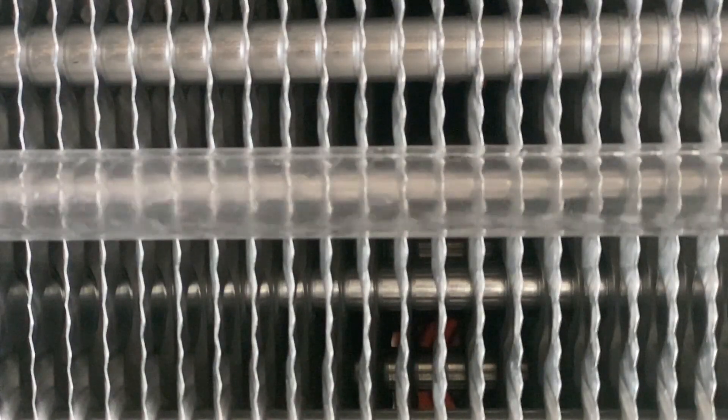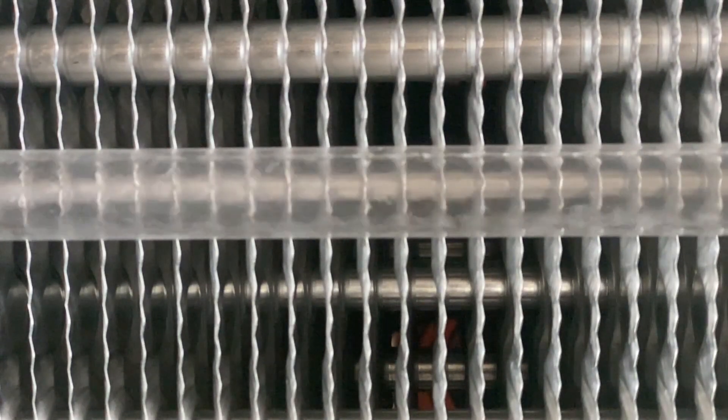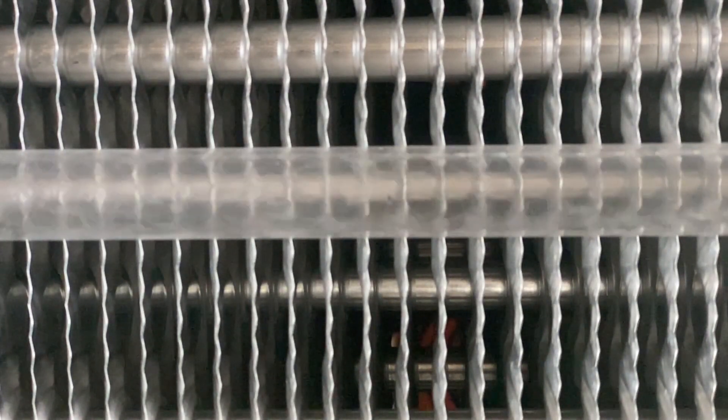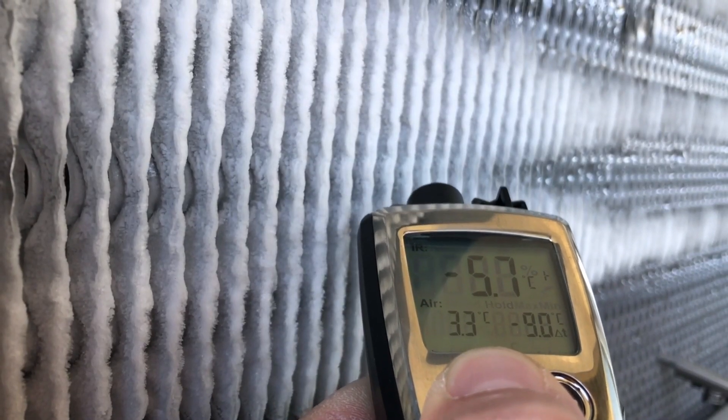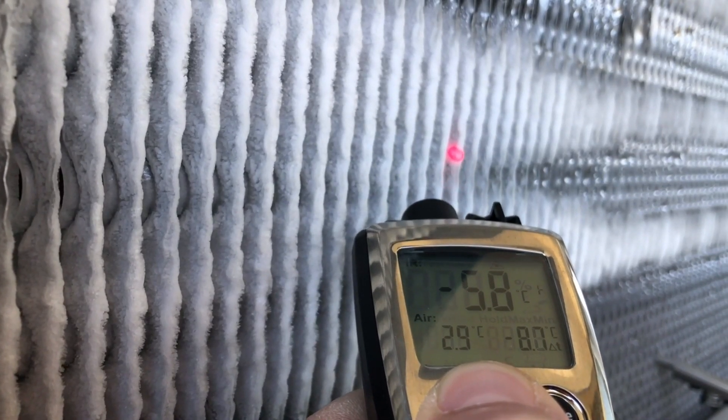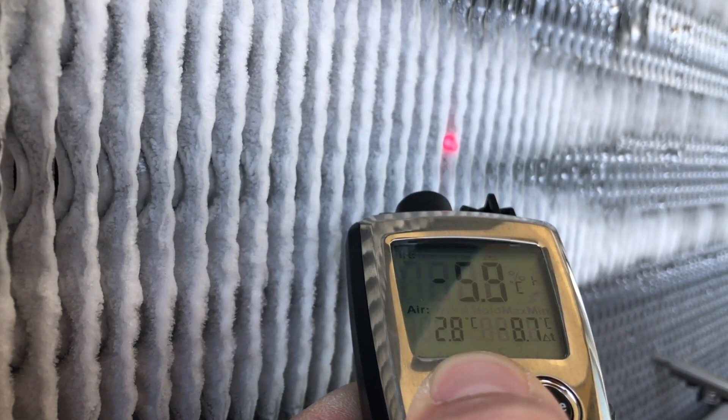This type of flow is a goal for many evaporator contractors in order to maximize the efficiency ratio. The increase of evaporation temperature will also decrease the delta with air temperature, which will limit the dehumidification phenomenon that implies a loss of capacity and ice formation.